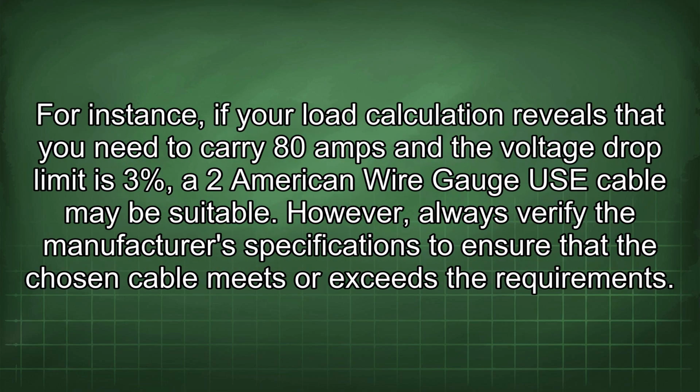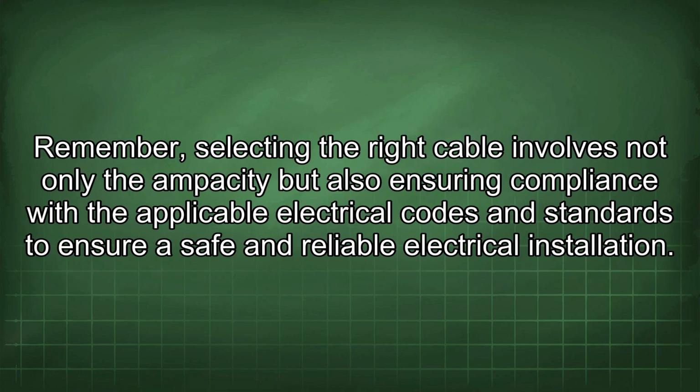For instance, if your load calculation reveals that you need to carry 80 amps and the voltage drop limit is 3%, a 2 AWG USE cable may be suitable. However, always verify the manufacturer's specifications to ensure that the chosen cable meets or exceeds the requirements. Remember, selecting the right cable involves not only the ampacity but also ensuring compliance with the applicable electrical codes and standards to ensure a safe and reliable electrical installation.